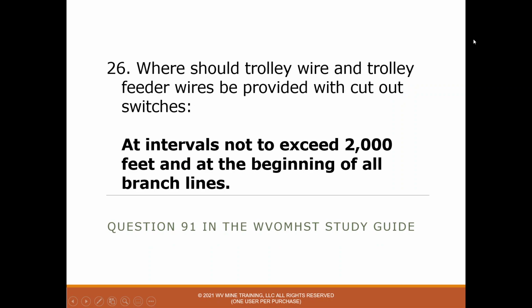26. Where shall trolley wire and trolley feeder wires be provided with cutout switches? And the answer is intervals not to exceed 2,000 feet and at the beginning of all branch lines. So a cutout switch on the trolley wire every 2,000 feet, and where it branches off to go to another section, at the beginning of that branch line.